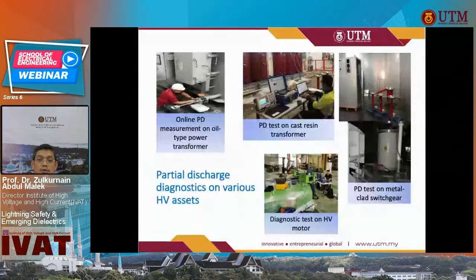Apart from gas, we also have various high voltage equipment, for example, motor and transformer here in our campus, all to be detected using special equipment, and also cast resin transformers. You can also detect the PD in advance before total breakdown occurs.